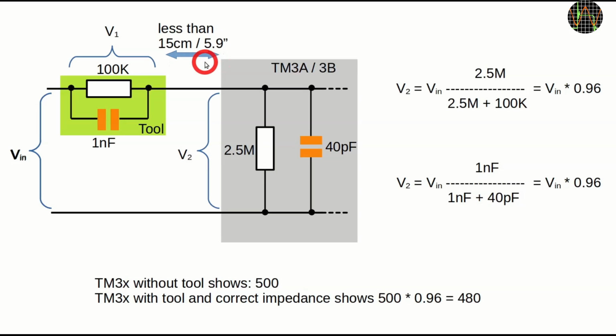To understand what it does, consider the DC and AC case separately. The meter doesn't actually measure DC, but at very low frequencies the capacitors have a very high impedance and can be ignored. So at DC we have a voltage divider consisting of the 100K of the tool and the input resistance of the TM3X, which should be 2.5 megohm. If the input resistance has indeed this value, adding this tool will drop 4% of the signal, leaving only 96% to reach the TM3X.